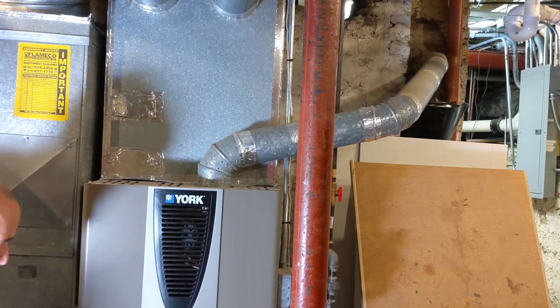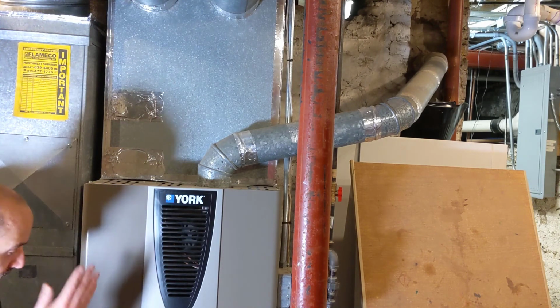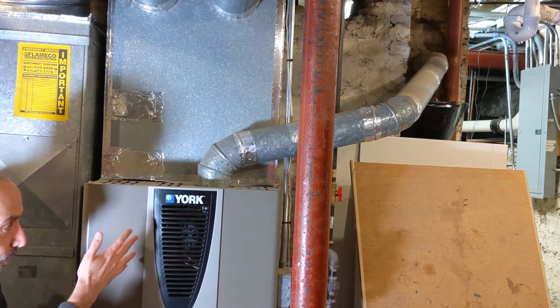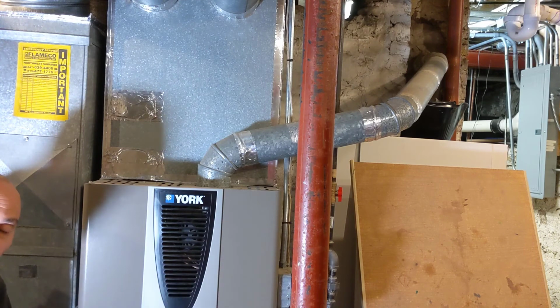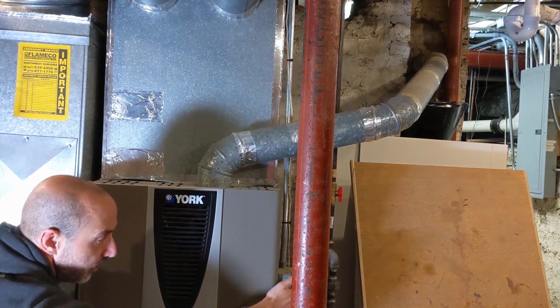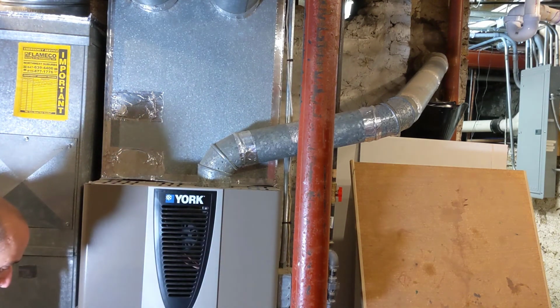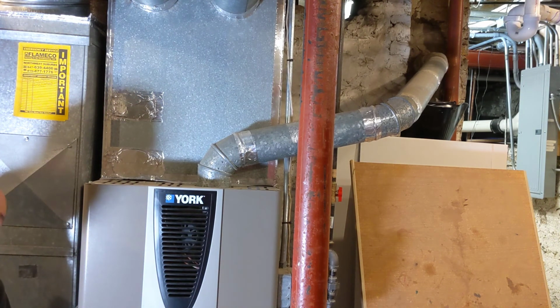Thanks for joining me on my annual furnace maintenance. Now that I've got it all buttoned up, I got the new filter in, we've cleaned the flame sensor, we cleaned the inducer port, and I set the thermostat to call for heat, so I'm going to go ahead and turn it on. And we're running. Now we're good for another season.